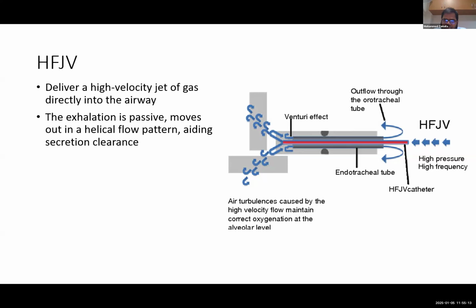Through that piston, while retracting, it is pulling the air outside. That is the active expiration in high frequency oscillatory ventilation. But in high frequency jet ventilation, exhalation is passive. It moves out in a helical flow pattern around the central core of the oxygenated air, and it helps in better secretion clearance. So that is the basic difference between high frequency jet ventilation and high frequency oscillatory ventilation.